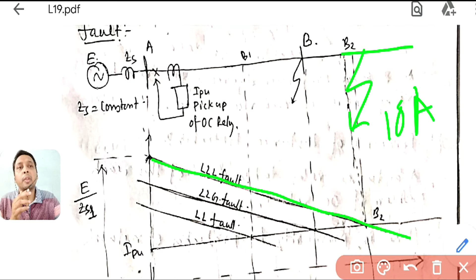Triple L fault, because it will give a very high value of current. So even if your fault is very far away at B2, you will still get 10 ampere. Here you will get more, 20, for a triple L fault. Because a triple L fault is more severe, it will give more current. So you can have 10 ampere current up to here.